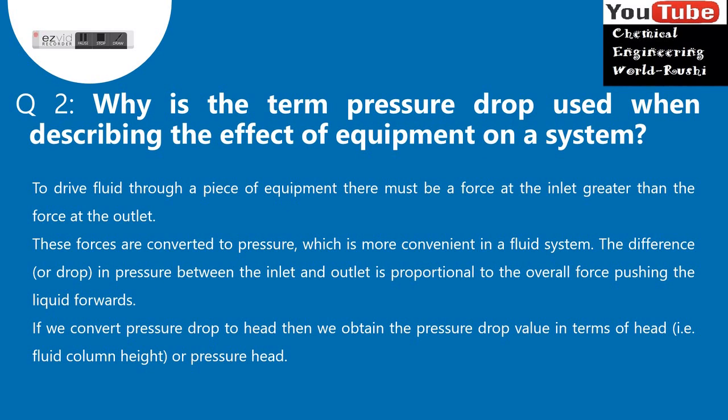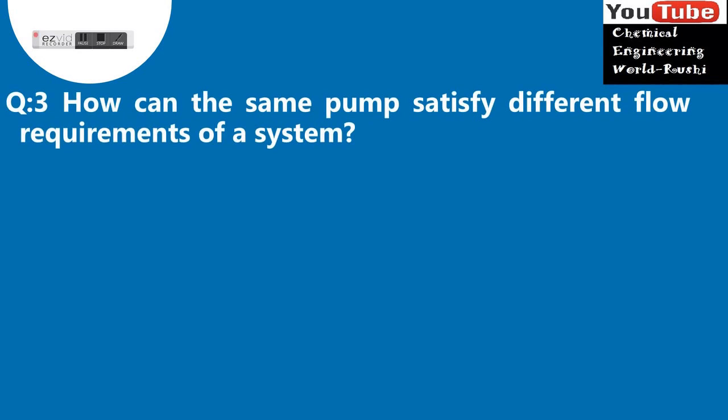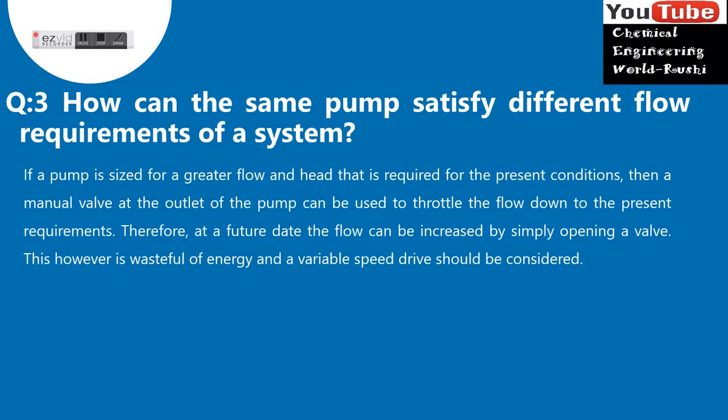Question 3: How can the same pump satisfy different flow requirements of a system? If a pump is sized for a greater flow and head than is required for the present conditions, then a manual valve at the outlet of the pump can be used to throttle the flow down to the present requirements. Therefore, at a future date the flow can be increased by simply opening a valve. This however is wasteful of energy and a variable speed drive should be considered.